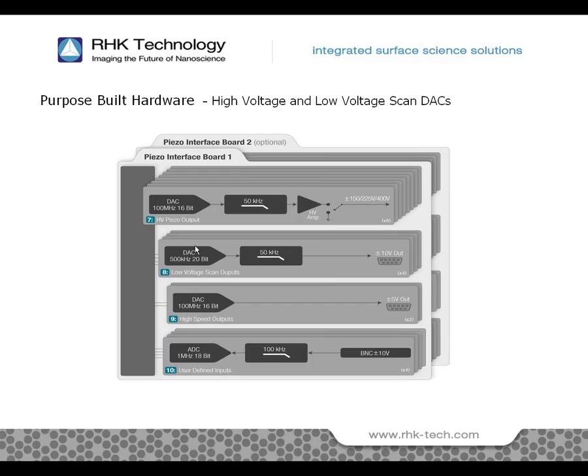An additional 4 DACs are provided with low voltage outputs. These are provided to interface to a scan stage that is an integrated power supply. 4 ADC inputs are provided for reading a scanning stage's position sensor to allow for closed-loop operation. It's not likely that anyone will use all of these capabilities at once, but as your experiment grows in sophistication, it's good to know that your controller will not limit what you can dream to explore.